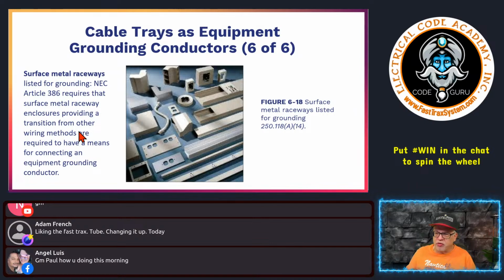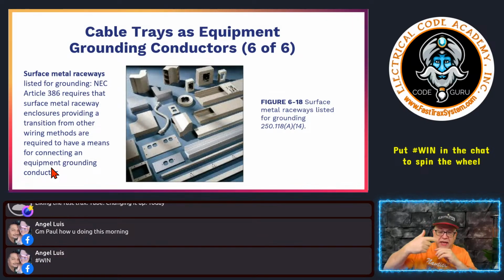You still follow the same rules. Typically, this is probably going to be all the same stuff that you would do in 250.96, okay? Well, it says when you make that transition from other wiring methods, they are required to have means for connecting an equipment grounding conductor. So if I'm using EMT and I'm transitioning into the surface metal raceway, and the surface metal raceway is all metal, then the fitting will go into the knockout and it'll have a lock nut, and that is okay under 250.96. These aren't service conductors, doesn't need that enhanced bonding, that type of thing.